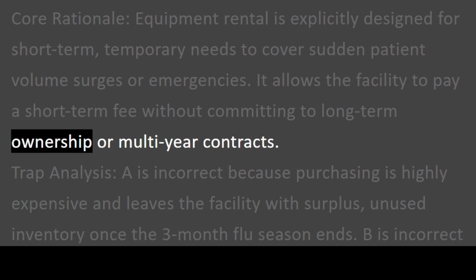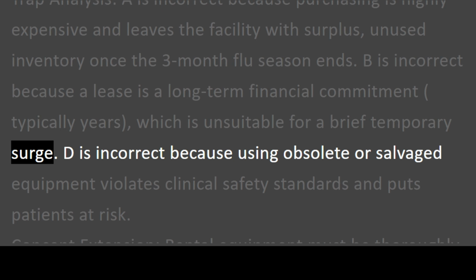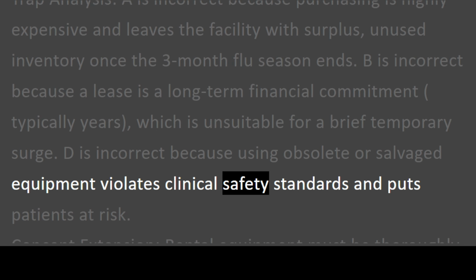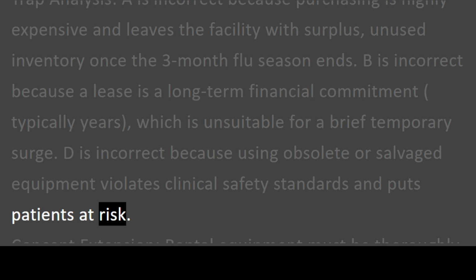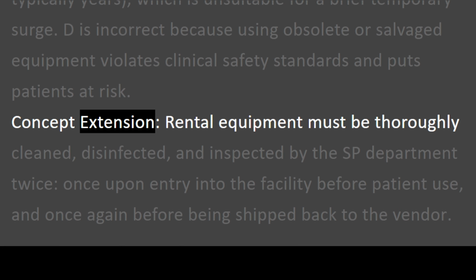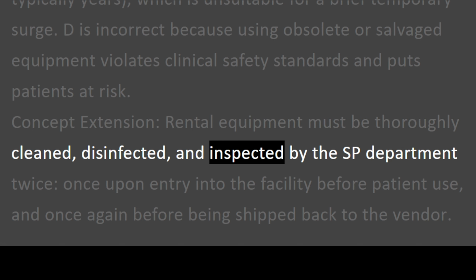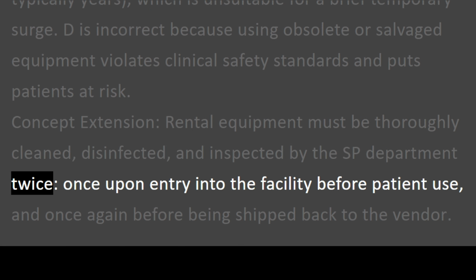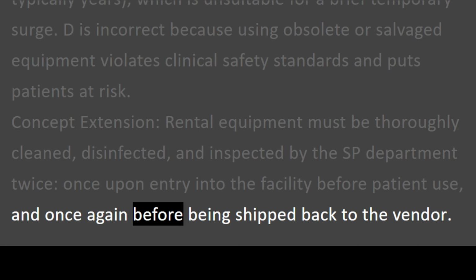B is incorrect because a lease is a long-term financial commitment, typically years, which is unsuitable for a brief temporary surge. D is incorrect because using obsolete or salvaged equipment violates clinical safety standards and puts patients at risk. Concept extension. Rental equipment must be thoroughly cleaned, disinfected, and inspected by the SP department twice, once upon entry into the facility before patient use, and once again before being shipped back to the vendor.